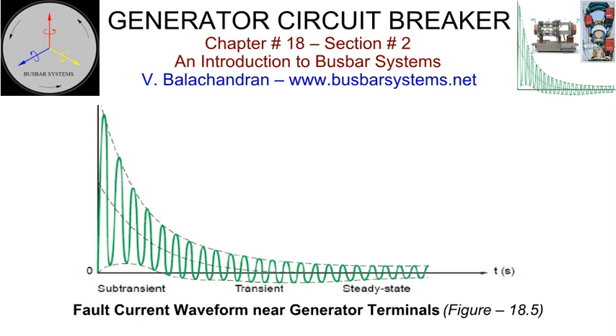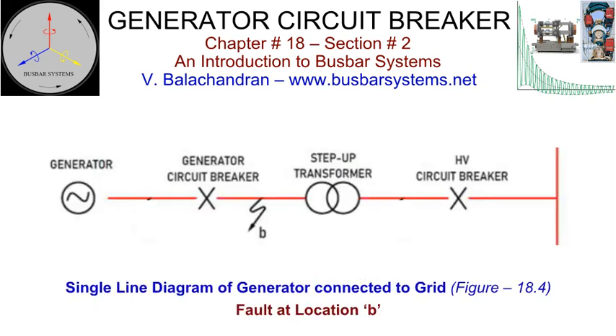A steady state or synchronous reactance Xd is attributable to the armature winding. The steady state reactance may vary from 150% to 230% for turbo alternator and 70% to 130% for a salient pole machine. An aperiodic component with a time constant TA is approximately 100 milliseconds. Location of fault at B: the fault is fed by the generator. Though the impedance of the generator is higher than the impedance of the generator transformer and consequently the magnitude of the AC component is lower, the DC component can exceed more than 100% under certain conditions due to the high X by R ratio. Therefore, the asymmetry is very pronounced and the quenching of arc initiated at the current zero location may take a significantly longer time. The arcing time could last several cycles and the breaker must be designed to withstand electrical, thermal and electromechanical stresses arising out of this delay. Location of fault at C: the severity of fault at this location is much less due to the inclusion of the generator transformer impedance.